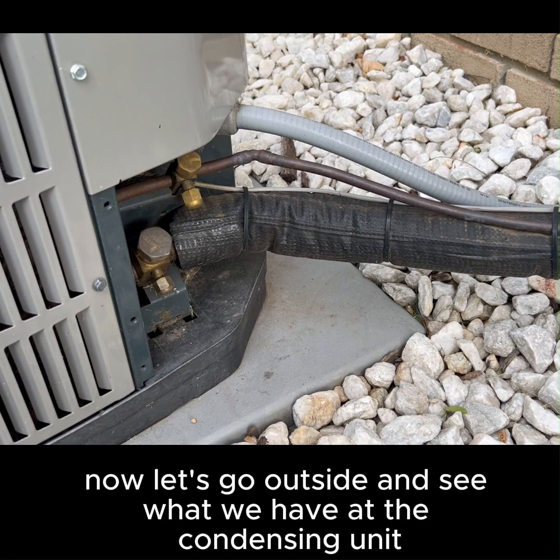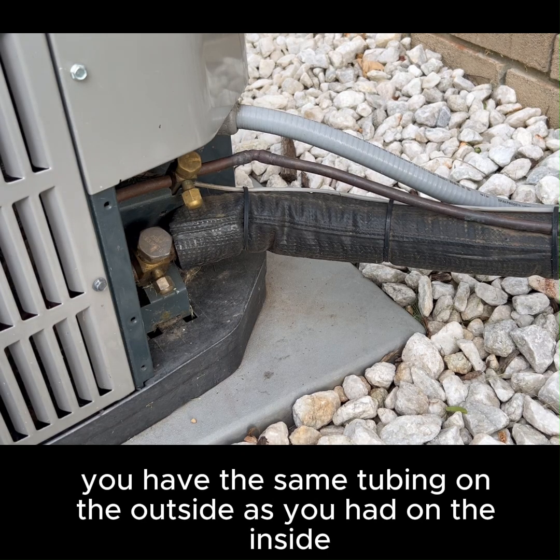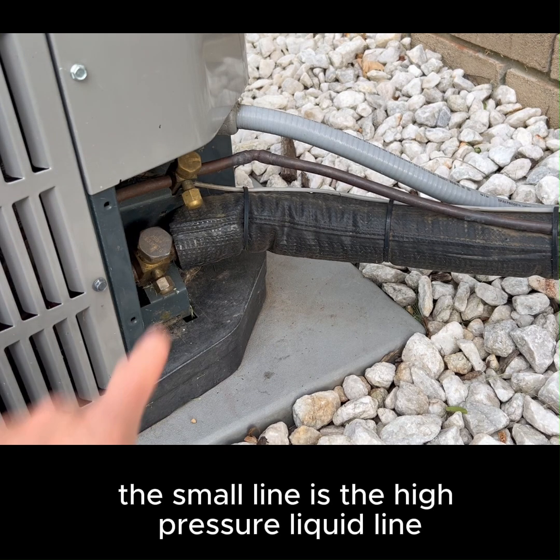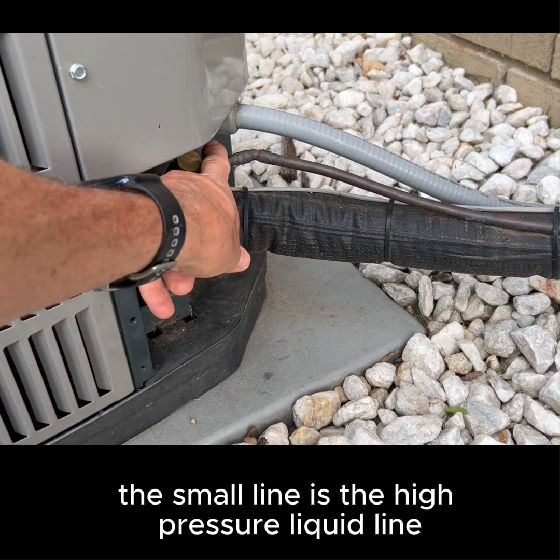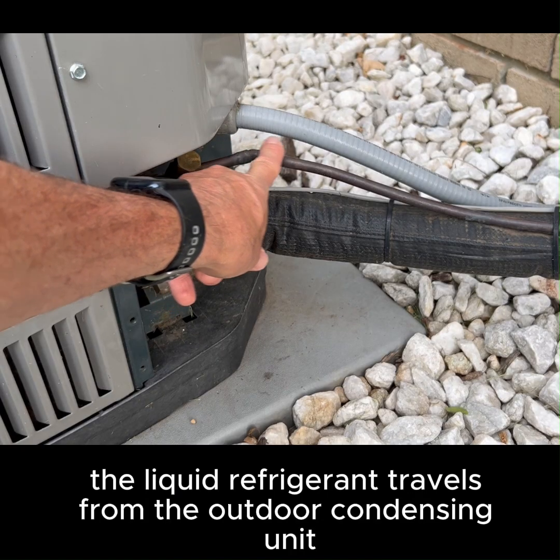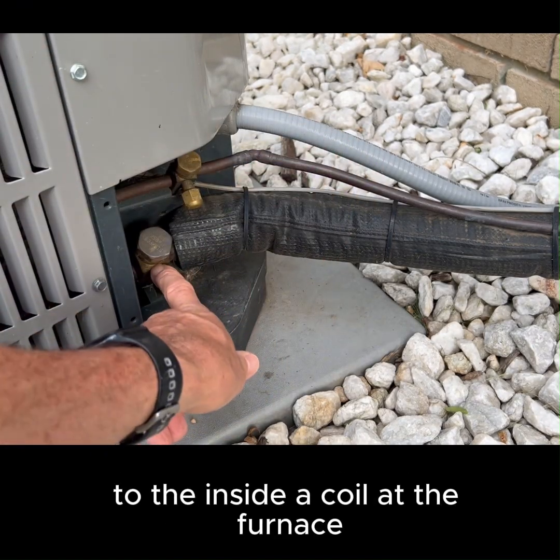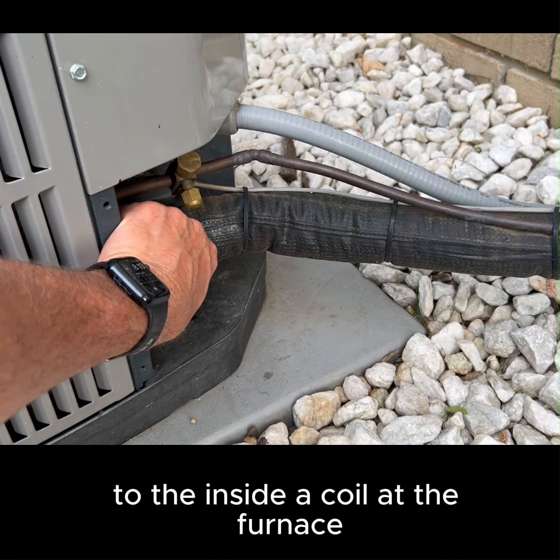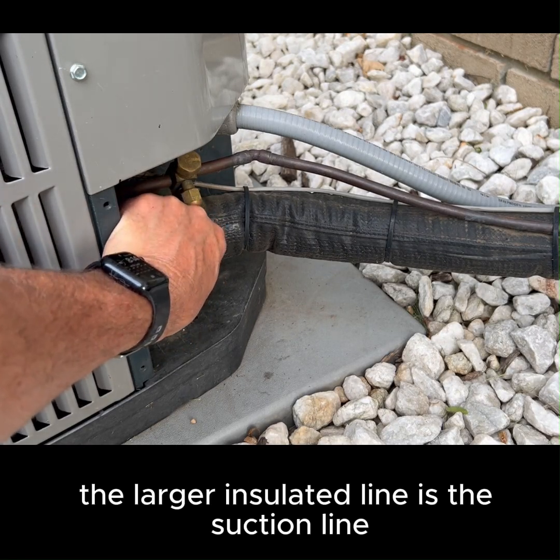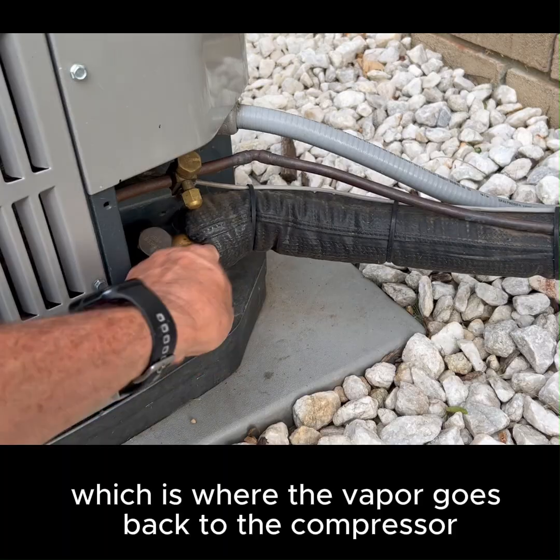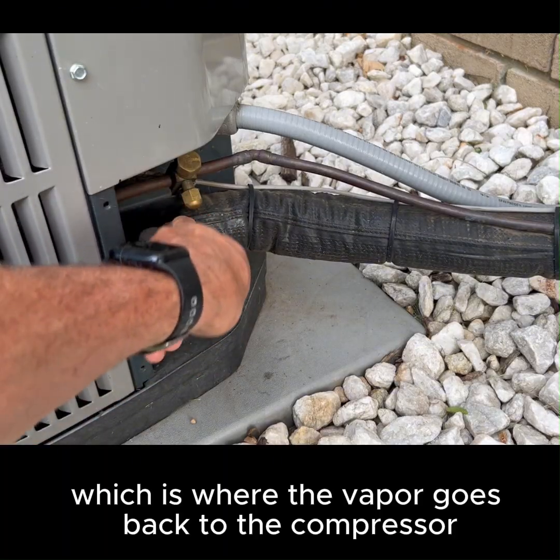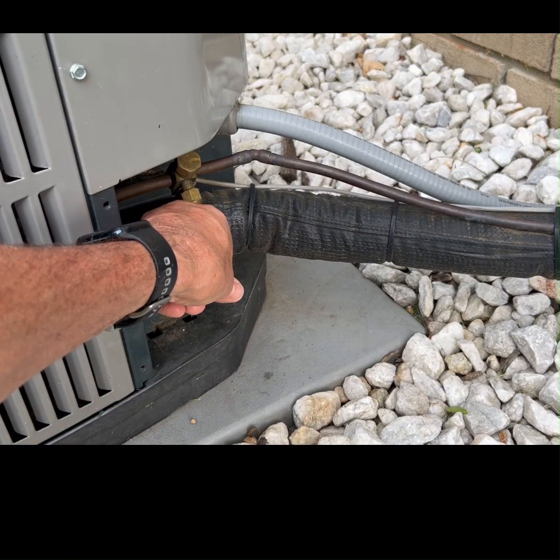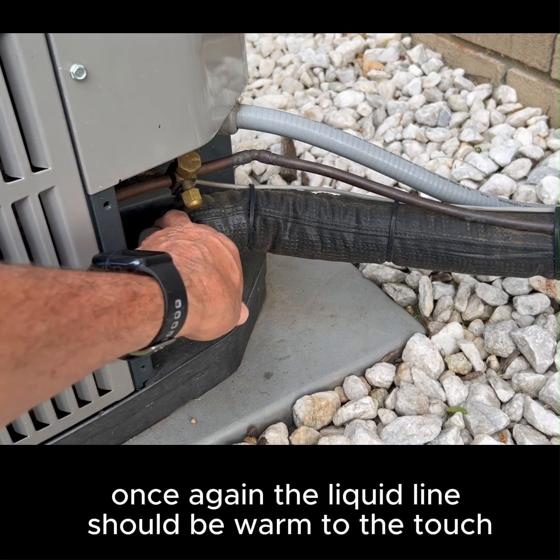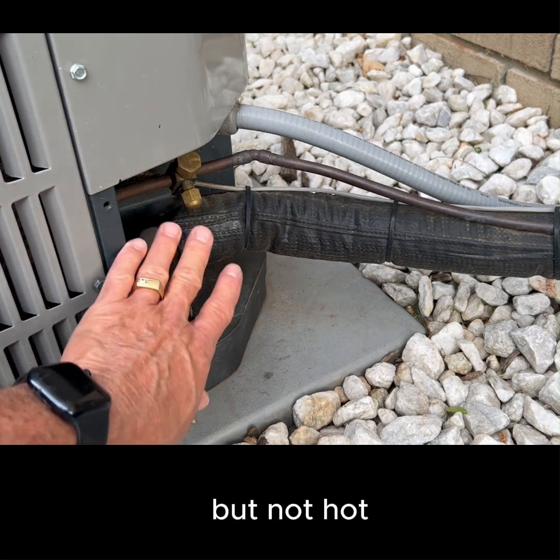Now let's go outside and see what we have at the condensing unit. As you can see, you have the same tubing on the outside as you had on the inside. The small line is the high pressure liquid line. The liquid refrigerant travels from the outdoor condensing unit to the inside A coil at the furnace. The larger insulated line is the suction line, which is where the vapor goes back to the compressor at the condensing unit. Once again, the liquid line should be warm to the touch, but not hot.